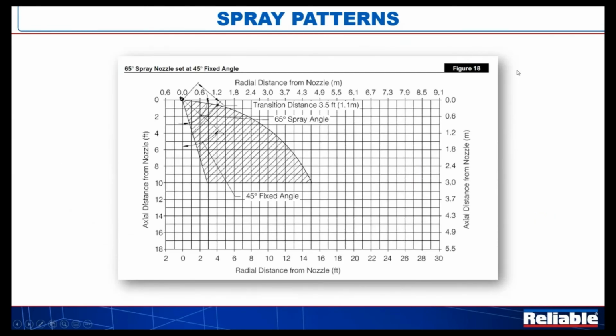So here is one of the figures, one of the 72 figures, 2-dimensional flat, looking at the side of this nozzle as it's spraying. This is a 65-degree cone, and it's set at 45 degrees off of 0, which again is pointing straight down. So imagine this thing, the next one would be 60 degrees, 75, 90. It would work its way up around the right side of the clock. And that's what generates these 72 charts. And are you going to need the charts? Perhaps, and we'll show you why I say perhaps in just a second. But let's take a look.